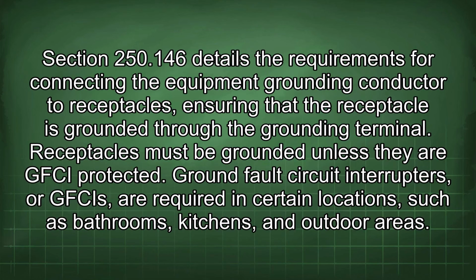Section 250.146 details the requirements for connecting the equipment grounding conductor to receptacles, ensuring that the receptacle is grounded through the grounding terminal. Receptacles must be grounded unless they are GFCI protected.